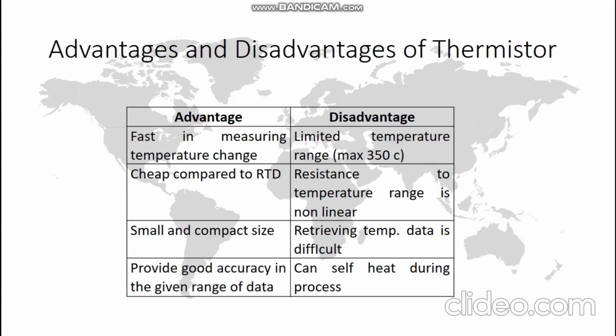Next we will talk about the advantages and disadvantages of thermistor. Firstly, it is fast in measuring temperature change. Second, it's cheap compared to RTD. Third, it is small and compact, and it provides good accuracy data in a given range only. The disadvantages are limited temperature range, and resistance to temperature is non-linear. Retrieving temperature data is also difficult due to the non-linear rate. And next, it can self-heat during the process.